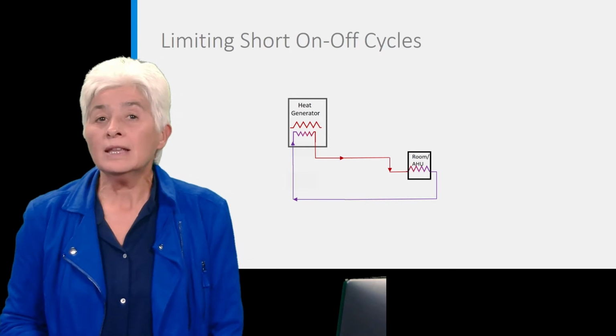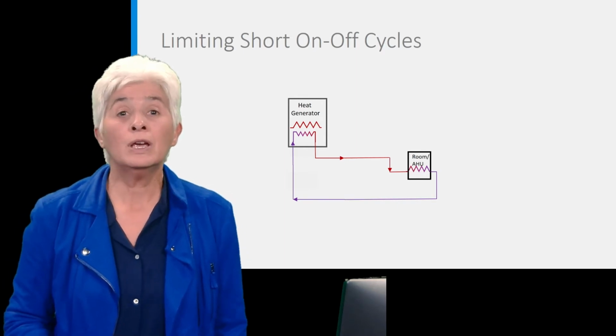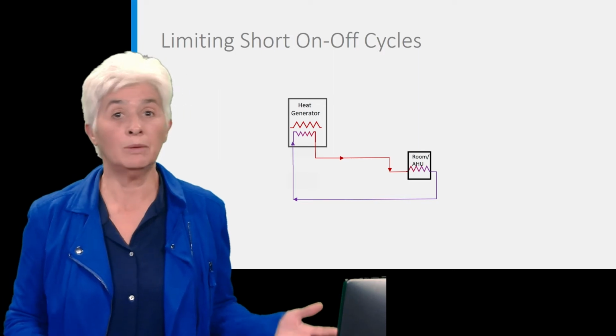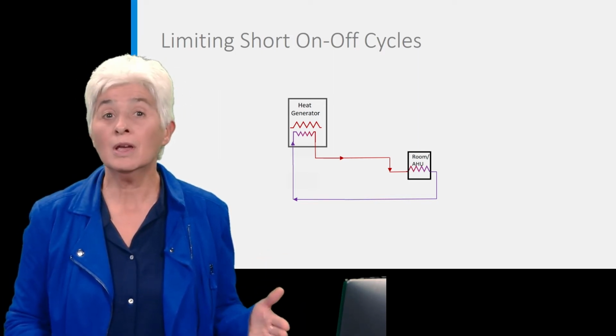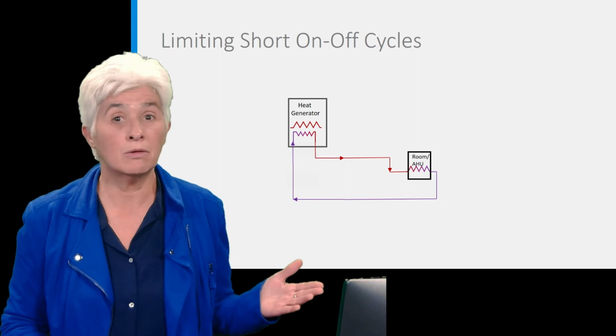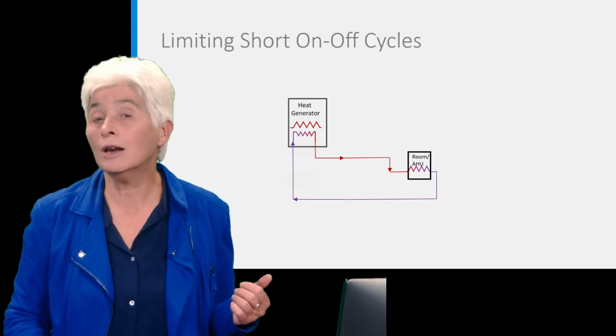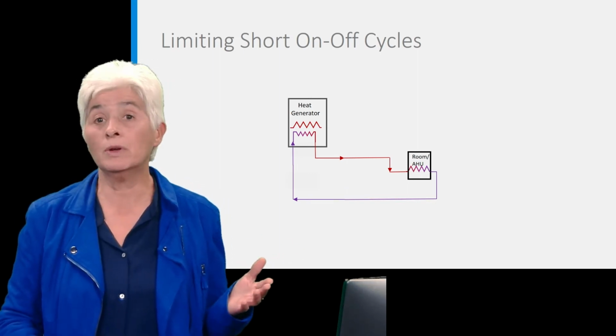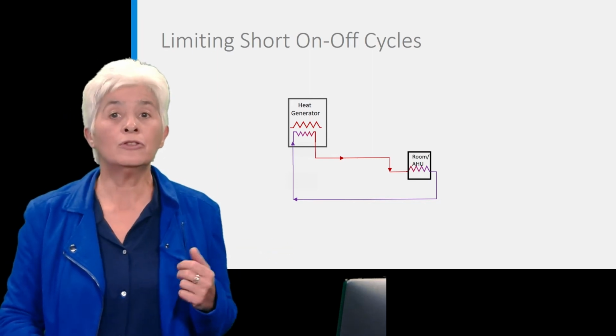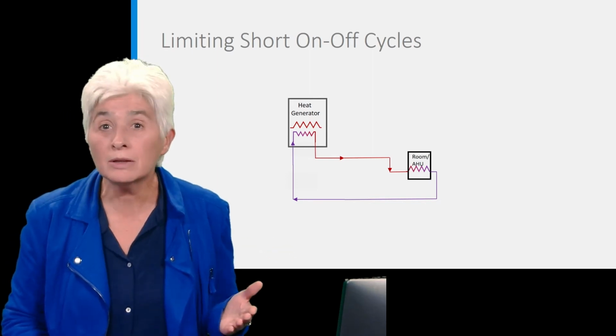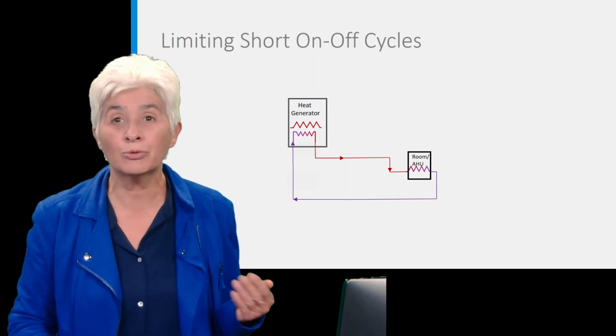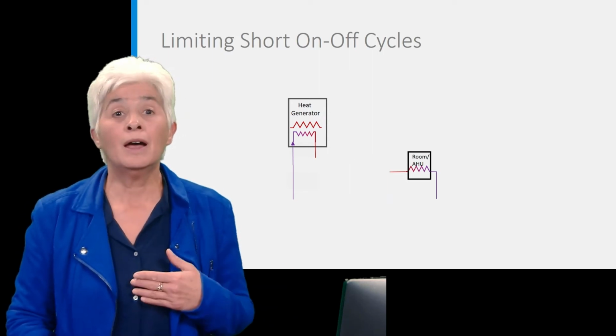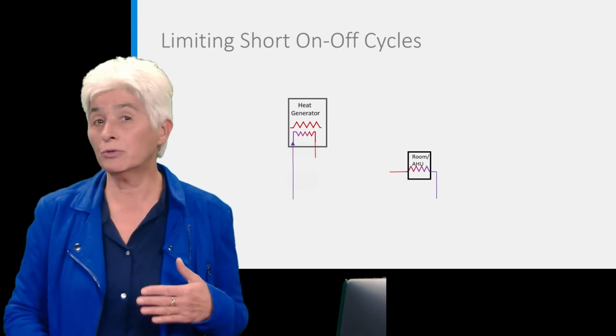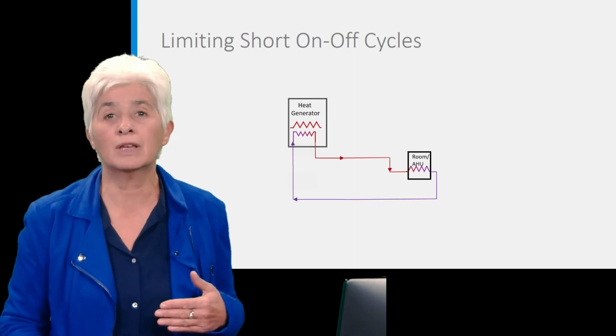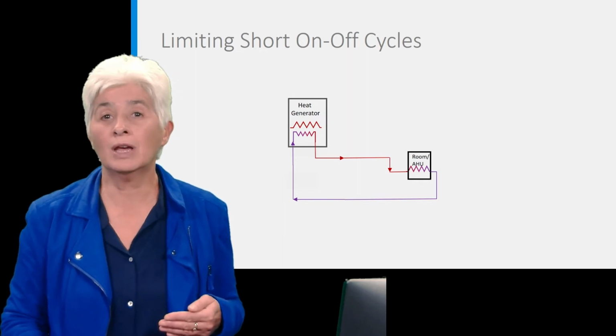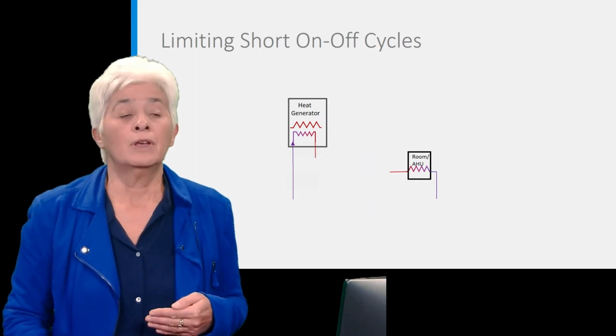If a lot of heating is needed in the room or the air handling unit, the heat generator, let's say a boiler or a heat pump, will be on for a long period, maybe continuously working for a few hours. But what happens if the heating load is low because the outdoor temperature is not very cold? Then the heat generator will go on for maybe 3 minutes, giving enough heat to bring the room at 20 degrees, and will then stop. And 5 minutes later, when the room temperature has decreased to 19.5, it will start again and will heat again for 3 minutes and stop and start again.